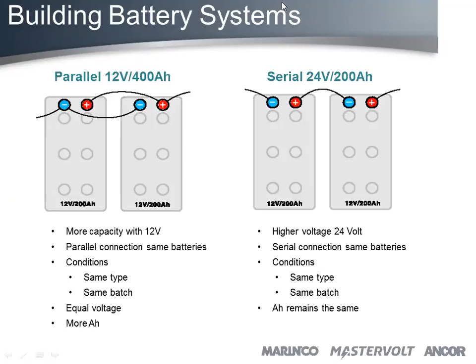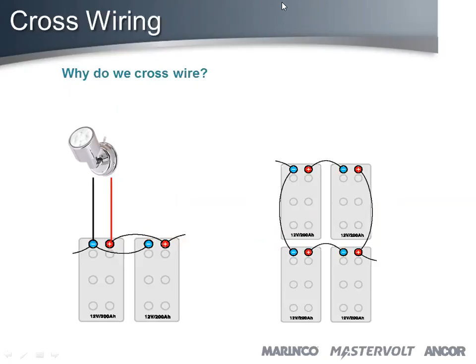Now, cross wiring — what's wrong with this picture? You're drawing the load off just one battery. That's one of the main issues we see in the field causing batteries to prematurely fail. Even though the cables are short, they still create resistance, so every time you charge or discharge, one battery works less hard than the other, and that battery will most likely fail within half of its life.